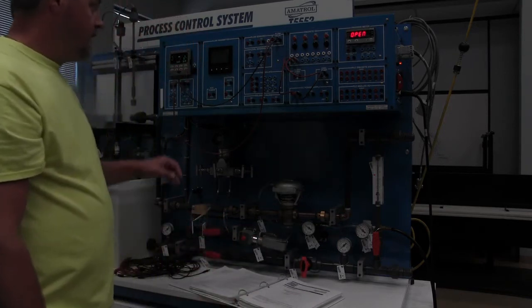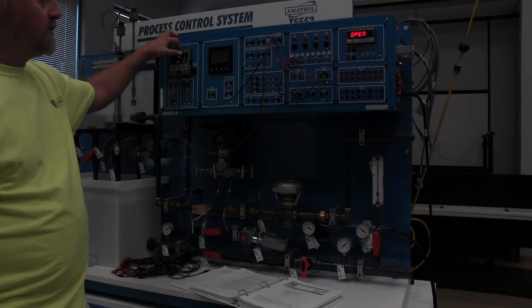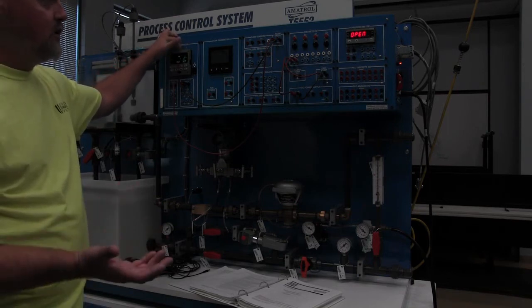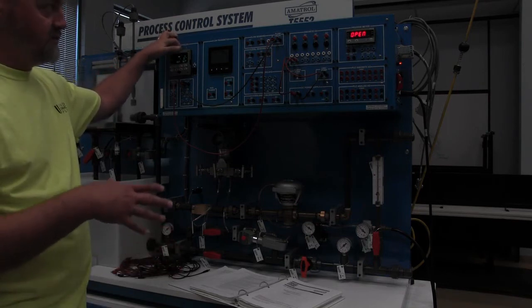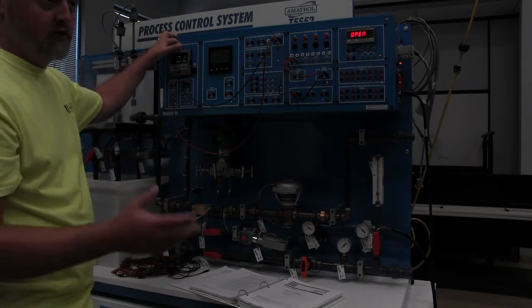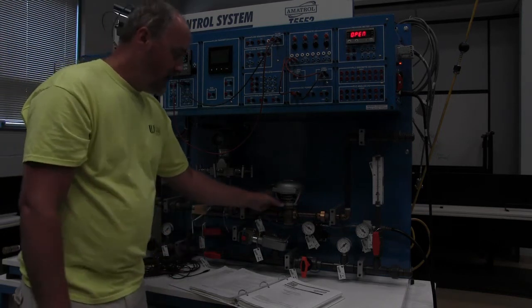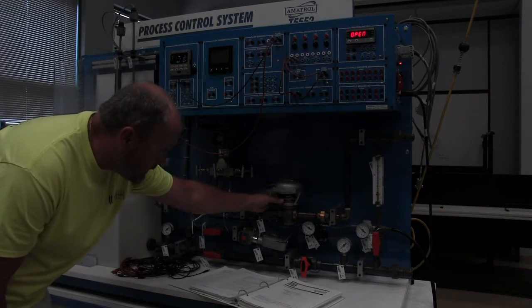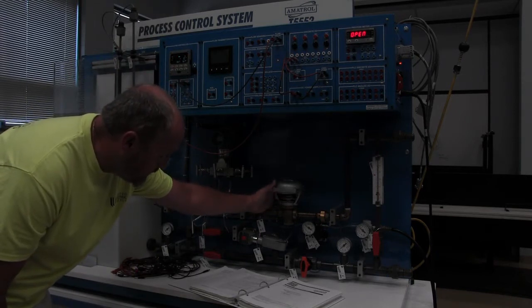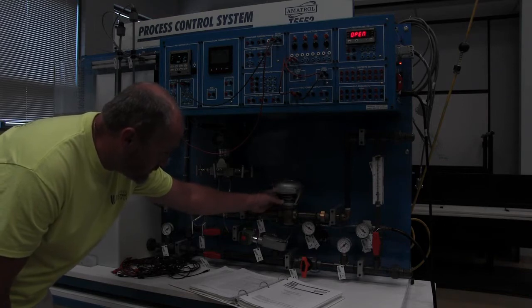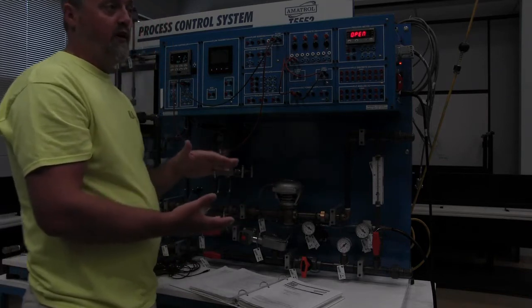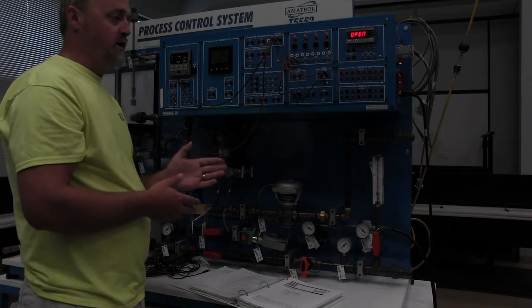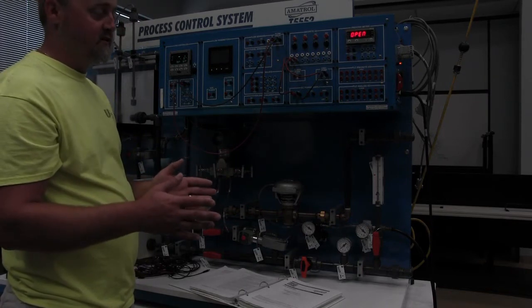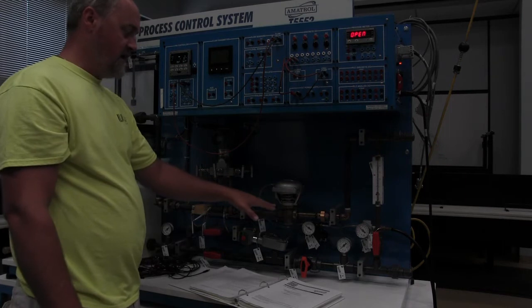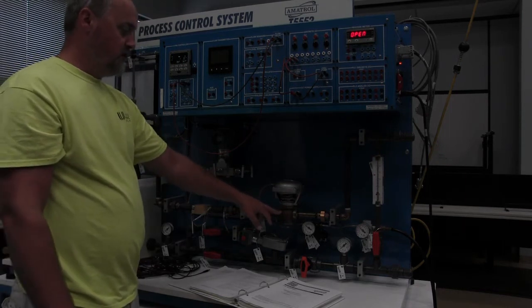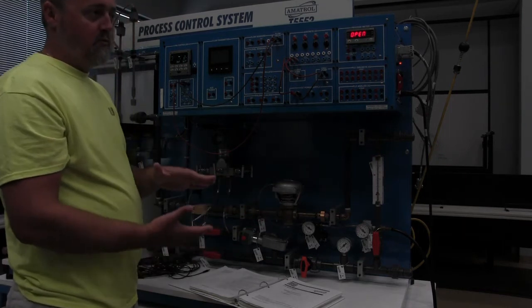If for some reason your scaling wasn't correct, where your 4 milliamps was either fully open or fully closed, and your 20 milliamps wasn't fully open or fully closed, the opposite of the 4, you actually have some adjustments on these air actuator valves. You can adjust it tighter on the diaphragm or looser on the diaphragm to give yourself more flow. If at 4 milliamps you wanted 0 and at 20 you wanted 100 gallons a minute, you could adjust the spring on the diaphragm to open and close this valve only to a certain portion.